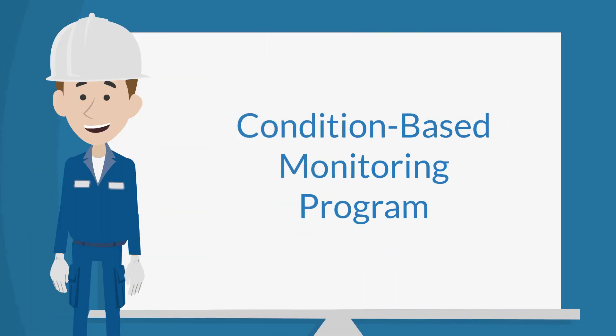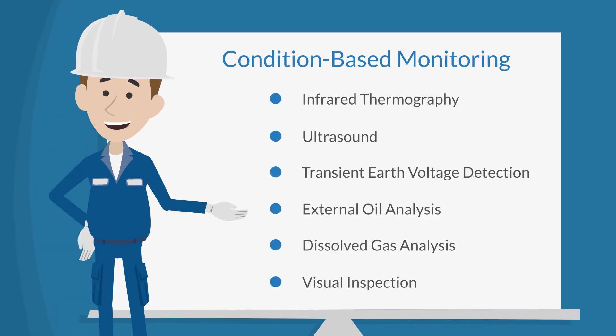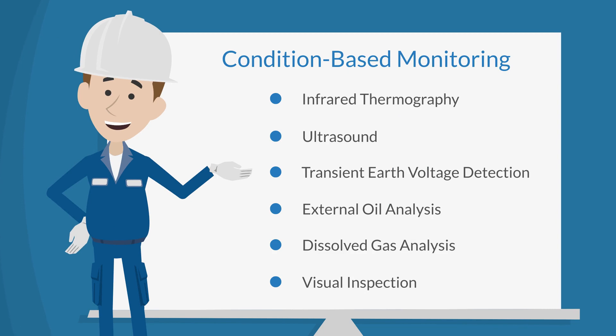Condition-based monitoring with available technologies is key to avoiding a transformer failure and unplanned power interruption. They allow the maintenance team to detect early warning signs of failure, facilitate replacement, and allow budget planning for the company. These technologies include infrared thermography, which detects loose connections, crimps, and cable creepage.